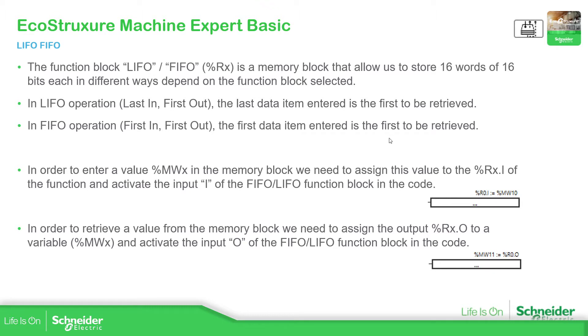In order to enter a value or a variable into the FIFO or LIFO function block, we need to associate the percentage r, number of the instance, dot i for input, to a percentage MW variable. And in order to retrieve a value, we need to use the percentage r, number of the instance, dot o for output, to a percentage MW variable — so we can retrieve the data from the FIFO or LIFO function block.